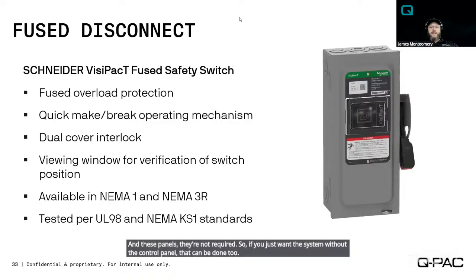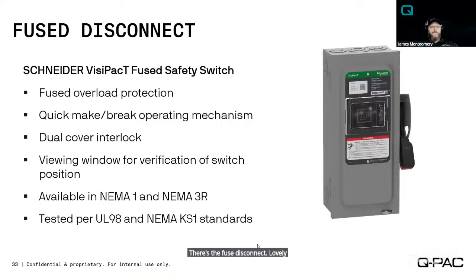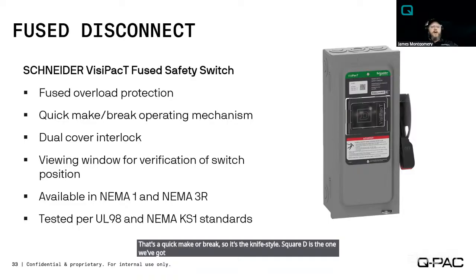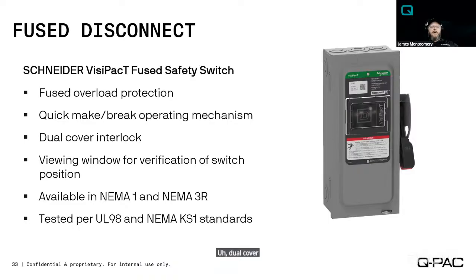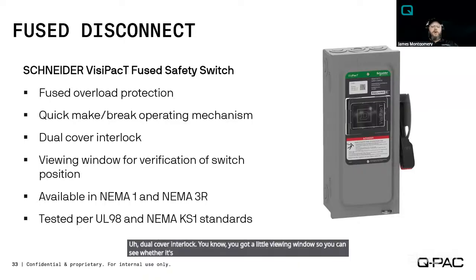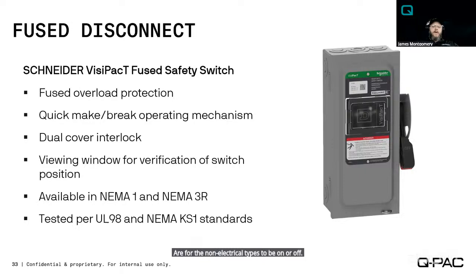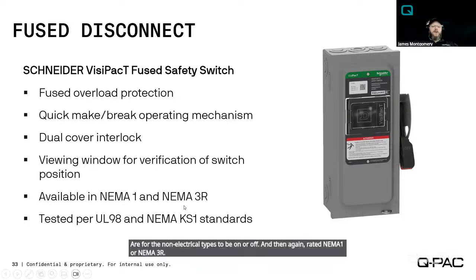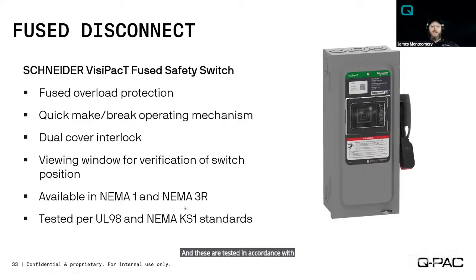There's the fuse disconnect. Lovely picture there. Fused overload protection. It's a quick make or break, so it's the knife style. Square D is the one we've got in the picture here. Dual cover interlock. You've got a little viewing window so you can see whether it's in the open or closed position, or for the non-electrical types, on or off. And then again, rated NEMA 1 or NEMA 3R. And these are tested in accordance with UL 98 and NEMA KS1 standards.